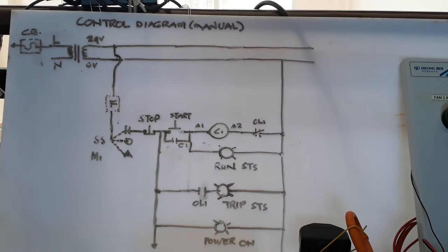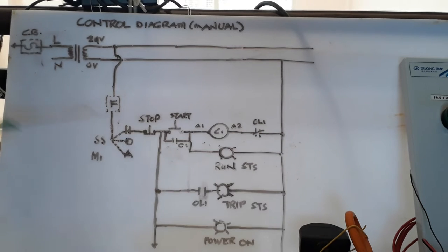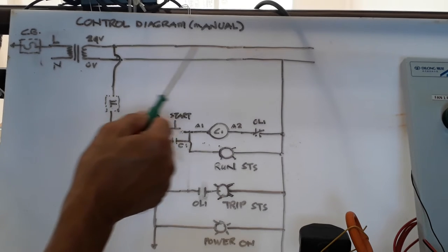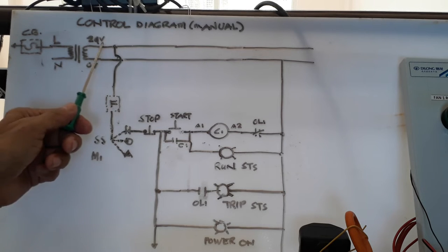Let me walk you through with my control diagram. As you can see here, I have a circuit breaker. My line is going to the primary side of my transformer — this is my control transformer. From 220V, because my power supply is 220V single phase, I put a circuit breaker. The primary side is 220V, then the secondary side of my transformer steps down to 24 volts. I extend the 24-volt line and the 0-volt line, which I can also call neutral.